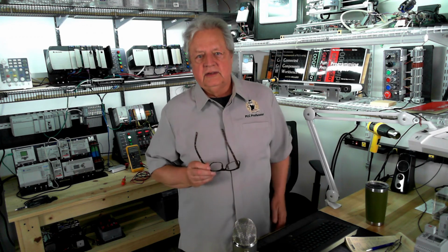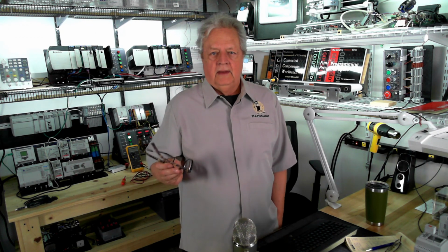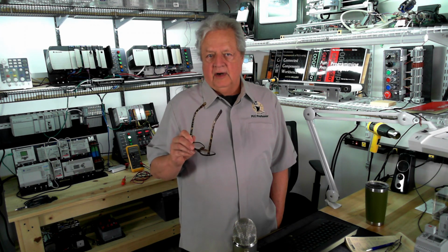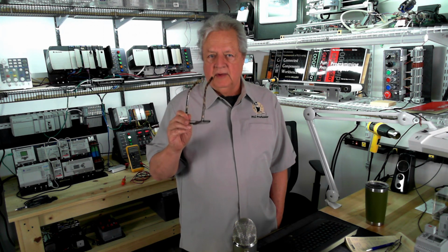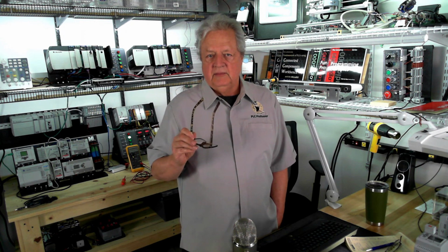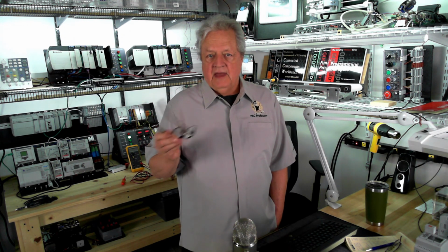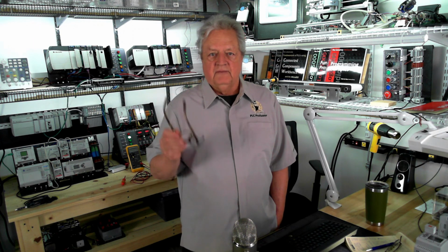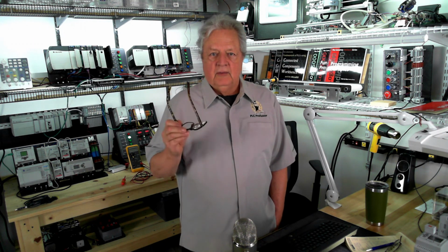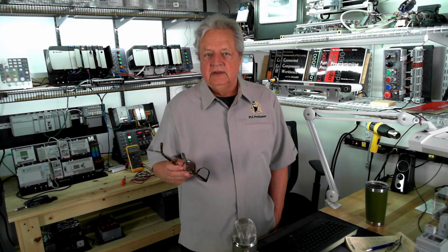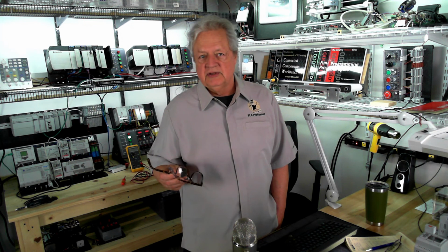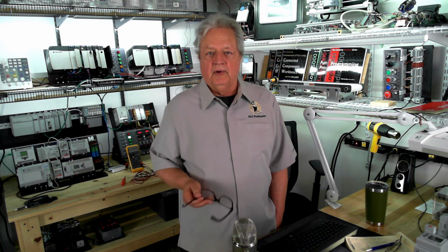As I said, this lab project was very simple. Now what you have is a program that primarily has a buffer inputs program, a buffer outputs program, and then something in between, maybe called a sequence. And that's where you would put your main program. I would save this with nothing in any of the program files except for buffer inputs and buffer outputs. I would save this as a template. That way, anytime you want to do a project where you have the I/O buffered, you just open this up, save it with a new name, and then start throwing your program in there.